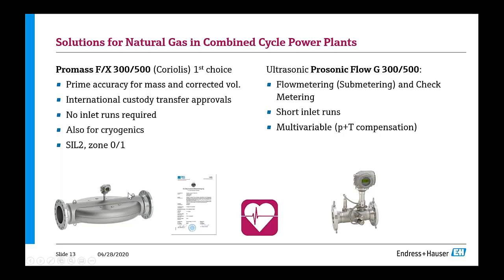These mass flow meters are also suitable for cryogenics, and they come with SIL 2, so for IEC 61508 or 61511 applications. Or here on the right-hand side, for submetering to the different power blocks, you may want to use a Prosonic Flow. That's an ultrasonic meter for check metering also, so checking such a custody transfer meter to see if it's still okay, or for submetering to the different power blocks. You have short inlet runs, and it's also multivariable, with integrated pressure and temperature compensation, as you can see here.